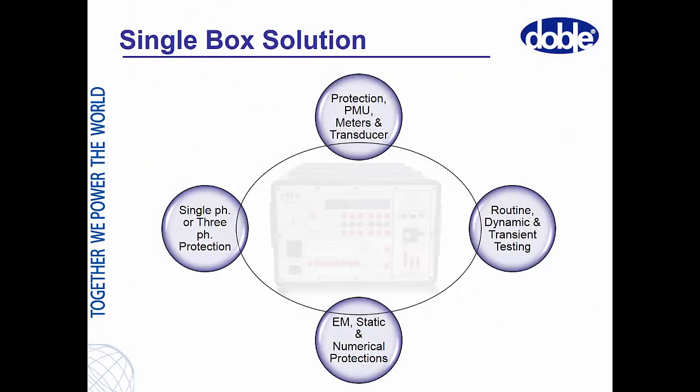The flexible design of this instrument provides configurable sources for up to 6 voltages and 6 currents along with 8 inputs and 8 outputs. This enables you to test all types of protection. It provides multiple sources to test numerical protection, and the sources can also be combined to provide the higher power required to test high-burden electromechanical relays. This is possible as the F6150 employs innovative switching power amplifiers, which provide compact yet powerful high-power sources.